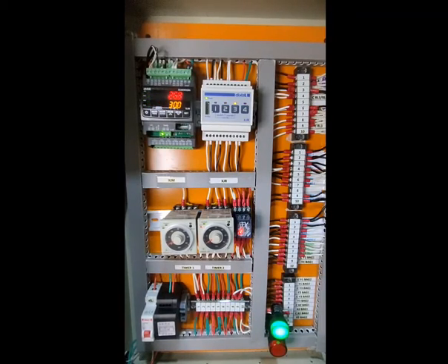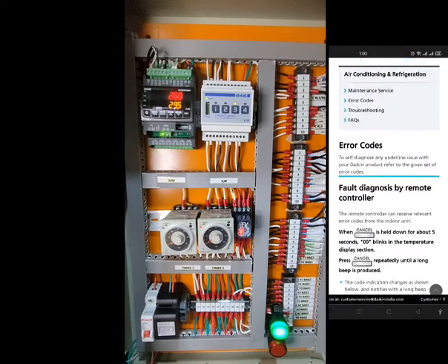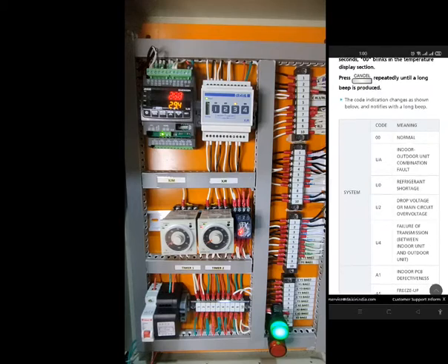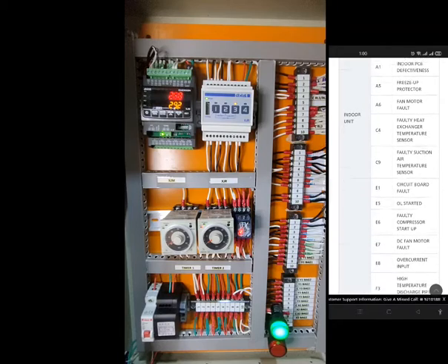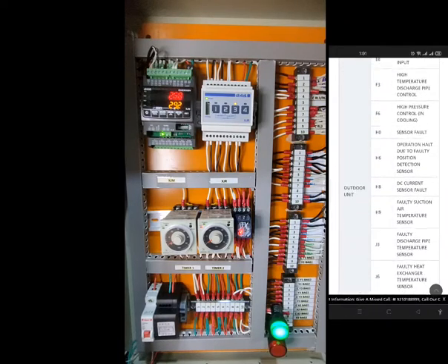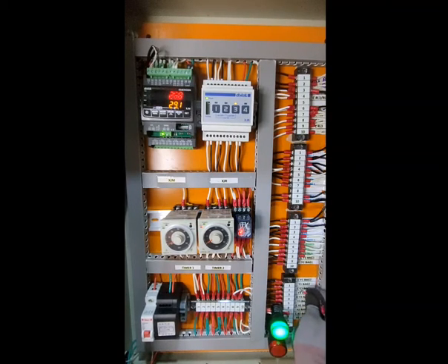Okay, as you notice, only unit 1 is running, so it's following the time schedule. If it happens that there is an internal error in the AC unit, the dedicated gateways of the AC units will produce alarm messages. Error messages will be captured by this control panel, which will force the other unit to turn on like this. So whenever there is an active alarm like this coming from the gateway, it will force the 2 units to turn on.